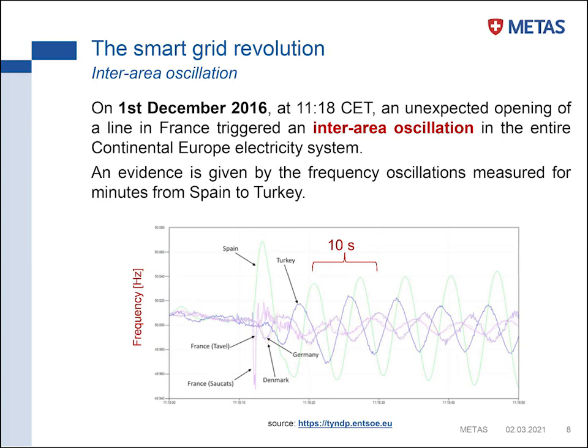One of the main ideas is that you have to imagine that our system is like some balls connected by some springs. When you excite one of the springs, all the other springs will start to oscillate, and the time the power flows from Portugal to Turkey and comes back, so from the two extremes of the network, from the most western part to the most eastern part of the network, creates an oscillation. So this 10 seconds corresponds to this kind of reflection of power going left and right all over the countries. Then obviously the system is much more complicated than that. This is a very rough approximation of what is going on.